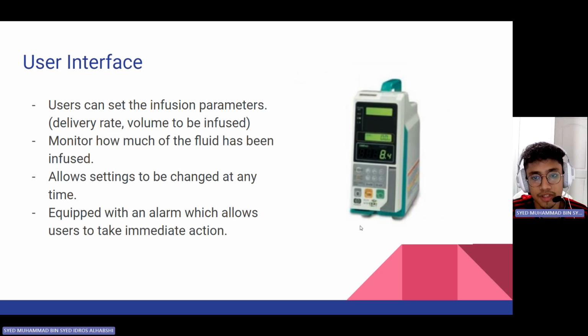Third, we have the user interface. Users can set infusion parameters such as the delivery rate and volume to be infused to suit the patient's needs via this interface. For delivery limits between 0.1 milliliters to 99.9 milliliters, the delivery rate can change from 0.1 milliliters per hour to 99.9 milliliters per hour. For delivery limits between 100 ml to 9,999 milliliters, the delivery rate can change from 100 ml per hour to 1,200 ml per hour.